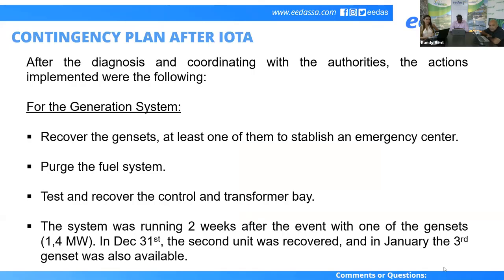What we did after we got communication with the islands: once the authorities developed the emergency plan, the idea was to recover the generation system as fast as possible. We made a basic assessment of the equipment. The generators had received some heavy rain, but were in good condition. So the drying process and all the measuring process to see if the insulation was working well started.